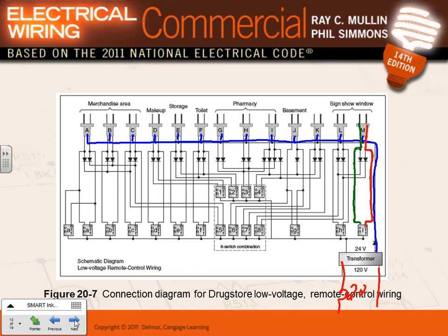You can see these diodes that they have, in this particular branch here. This one, to get you the master, I don't know if you can see the master here, going and energizing this fixture. Can you see that? The master, let me just draw one little thing here. If you take this master, I will go energize this fixture from this master. It's going this way, bam, and put some wire here. And the same thing from this master, I'm going to go right here and energize this. Now look at this fixture. This fixture has two ways of energizing it, either locally from this switch, or the master switch sitting next to the secretary, who can push that switch and turn this light on and off. So that's where the superiority of the low voltage system becomes a big deal.